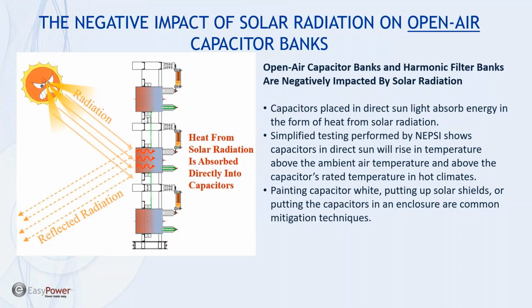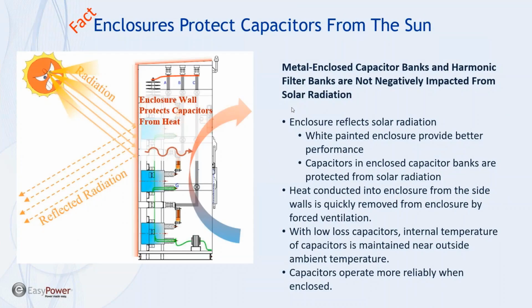That's because the heat is being absorbed into the skin of the car. Well, the same is true for capacitors. So when you have capacitors that are rated between 50 and 60 C, and the ambient temperature can be as high as, say, 40 to 45 C, it's easy to see that you can exceed the rating of the capacitor. So it's our opinion that metal enclosed systems allow capacitors to better operate in hot environments. We also have the ability to paint the enclosure white, which is another key option to keep the system from running warm. We can put air conditioning in if it's desired as another possibility.